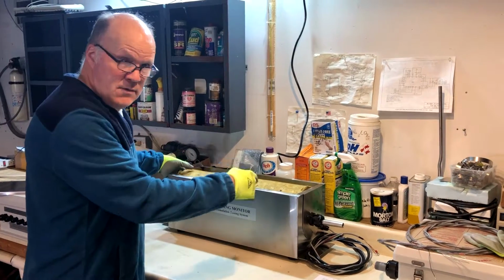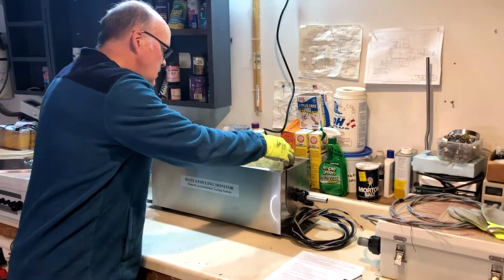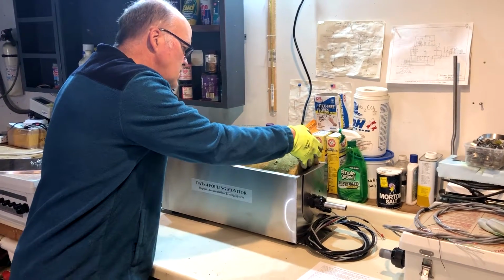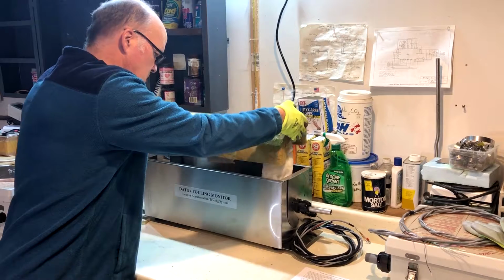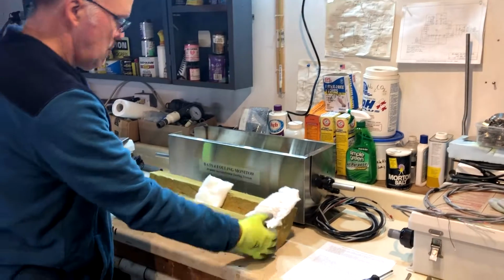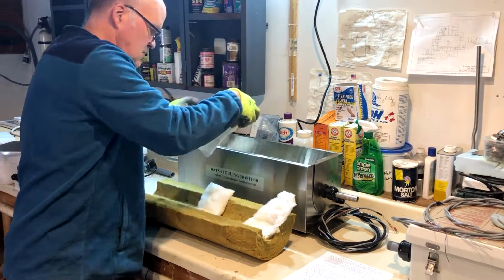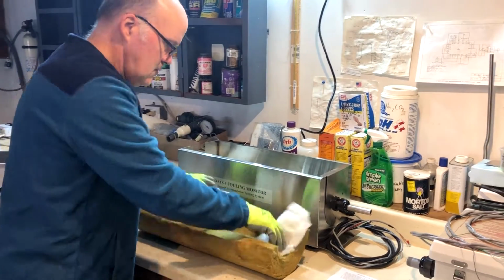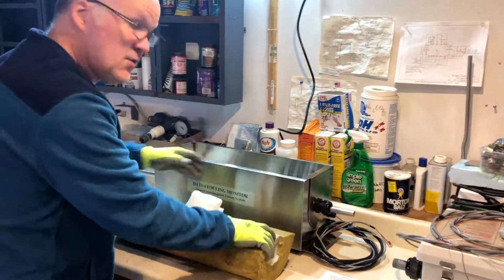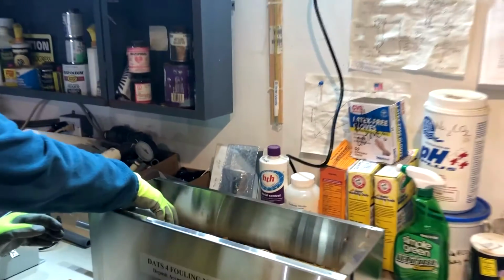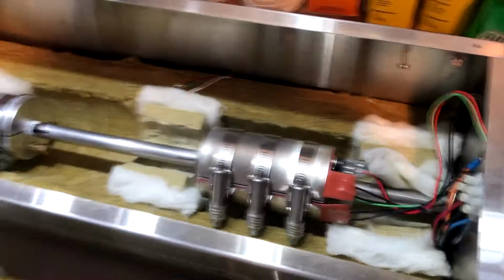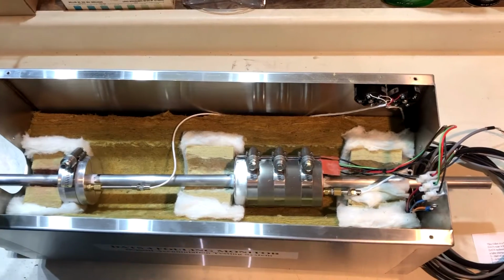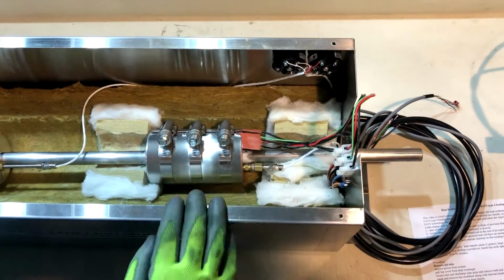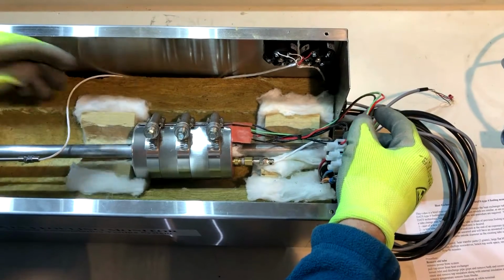Okay, to remove the main insulation, you need to rotate it out of the heat exchanger box like so, lifting it out. Some of the smaller insulation pieces will come out with this upper insulation, which basically looks like this. Now if you could come over and look right inside here, you'll see the heat exchanger core in place inside the system.